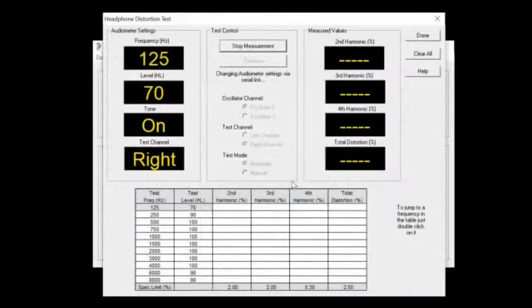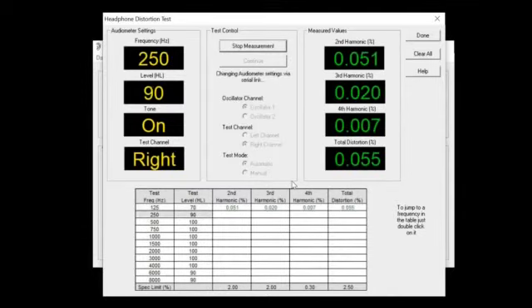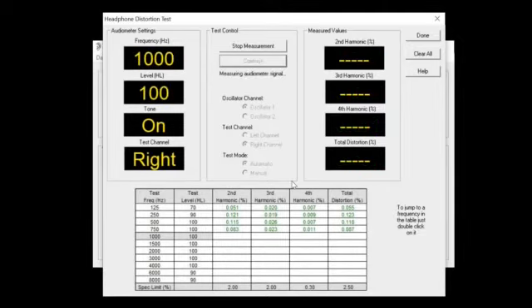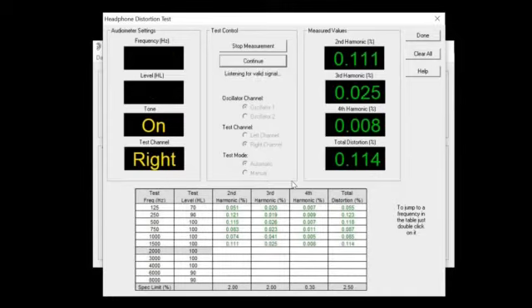I think I'm going to go back in. I'll wait and go on to the left here, and I'll show you how that can be readjusted, because this kind of moves right along. I could have stopped it and changed it and brought it around, but I'll show you that in the left ear. Now here, because this audiometer has all the frequencies starting in at 125, it's going through the full scope of them. I'll speed this up later on so that you don't have to sit here and listen to my boring conversation. And by the way, I hope I'm not getting scored on video proficiency, because if I am, we have a big problem. I'll accept scores on audiometer calibration, but not on video performance.